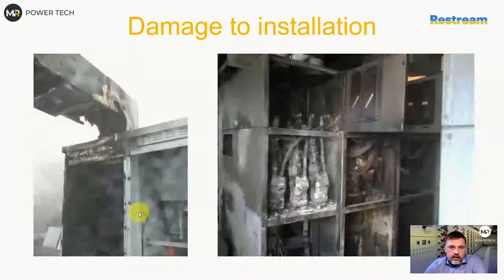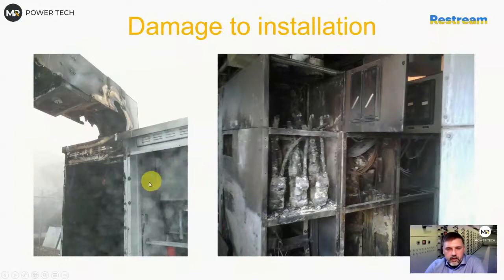But if you have a panel like, this is not a good picture, but for example an MCC, let's assume that was the main panel connected by busbar, and then you have a lot of feeders. Then this section will be your line. If this is 4B, it's separated as well. So this is your line, and then you consider the upstream protection. Generally, I do it all the time. I actually don't really remove line PD from the calculation. If you just take into account the breaker and consider that this breaker protects both sides, and this is line, this is not fully correct.